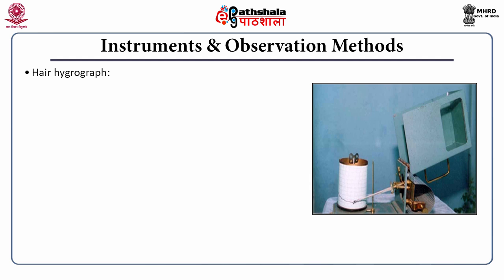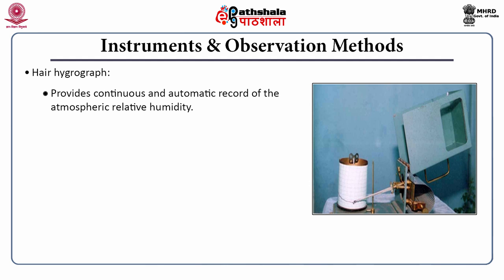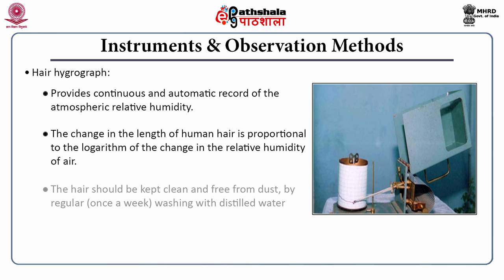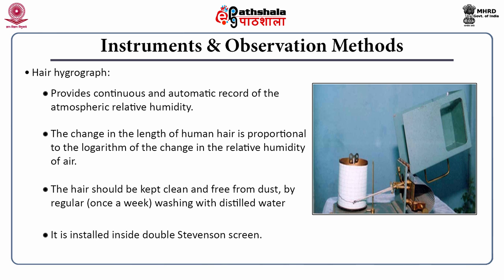The next equipment is the hair hygrograph. Hair is used as the sensing element because human hair is sensitive to the relative humidity of the air. Its length changes proportional to the logarithm of the changes in relative humidity. The hair should be kept clean and free from dust, and regularly washed with distilled water. This equipment is also placed inside the double louvered Stevenson screen.